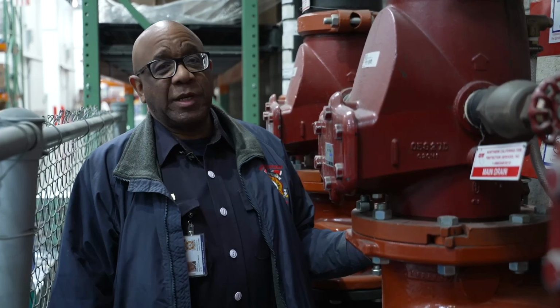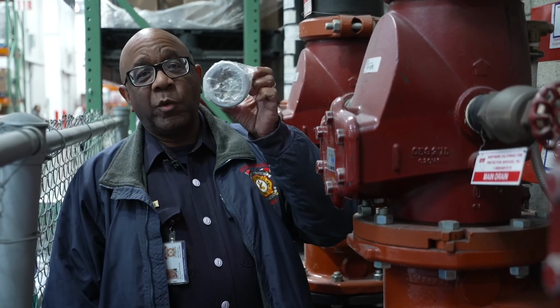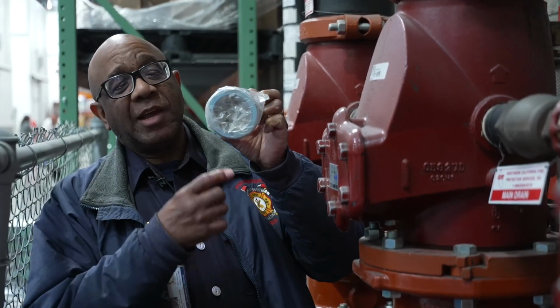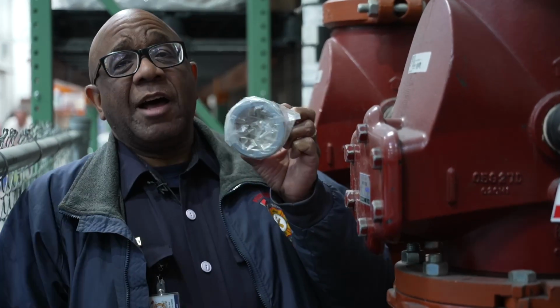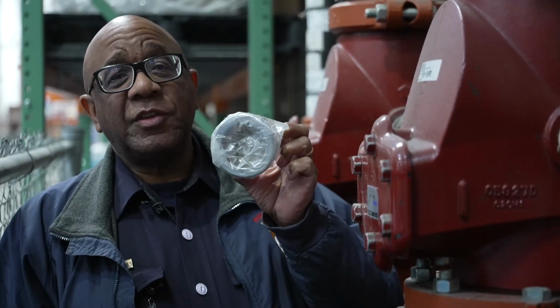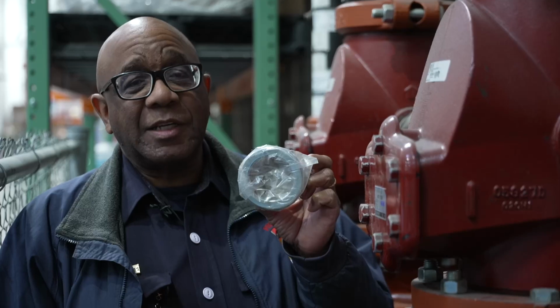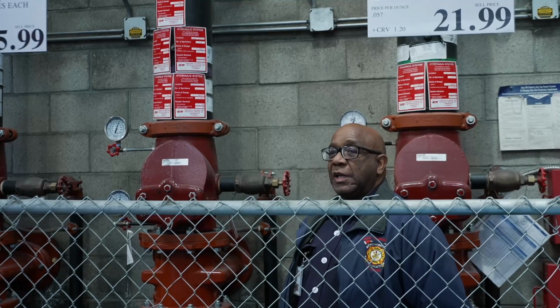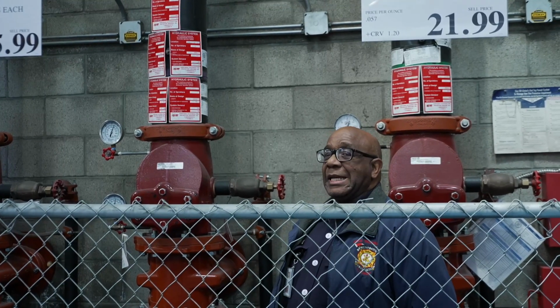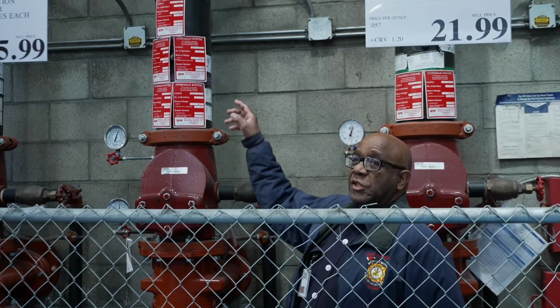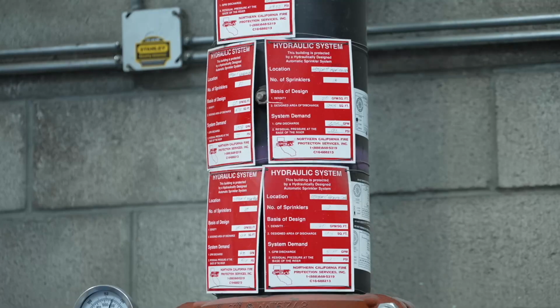When you have a large sprinkler system, there will also be areas where they have a suspended ceiling. In the suspended ceiling, to cover up the hole where the sprinkler comes through, you'll have what's called an escutcheon. They'll have various colors and types of these that will be near the spare sprinkler cabinets. Now with the hydraulic calc plates, each riser will usually have one. Sometimes they place all of them onto one riser, but they each will talk about a different section of the system that you're inspecting.